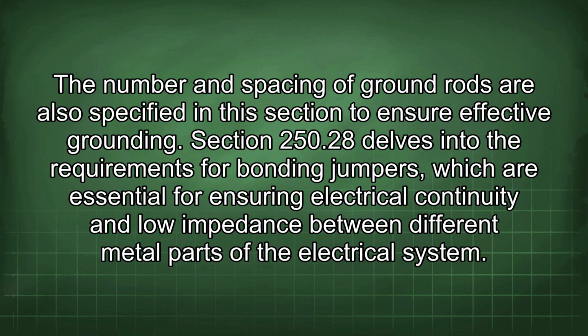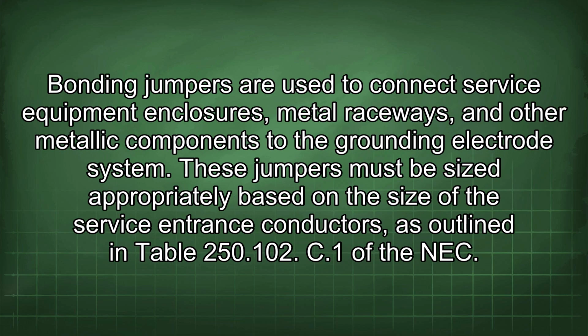Section 250.28 delves into the requirements for bonding jumpers, which are essential for ensuring electrical continuity and low impedance between different metal parts of the electrical system. Bonding jumpers are used to connect service equipment enclosures, metal raceways, and other metallic components to the grounding electrode system. These jumpers must be sized appropriately based on the size of the service entrance conductors as outlined in Table 250.102(C)(1) of the NEC.